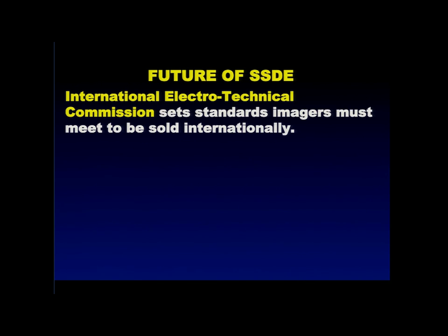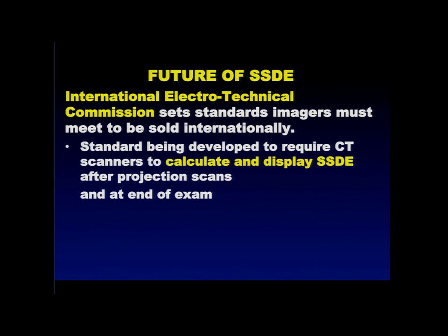What's the future of SSDE? Is there a future? Well, those of us that developed it from the very beginning thought it was only an interim solution until someday we had organ doses, but we don't know when that's going to be. So the IEC is the international organization that sets the standards that all CT imagers have to meet to be sold internationally.